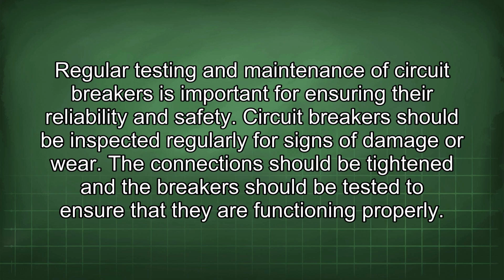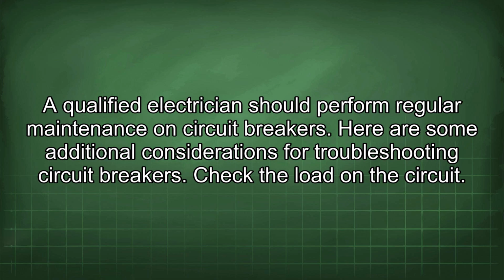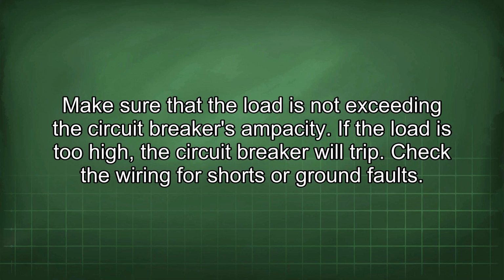Circuit breakers should be inspected regularly for signs of damage or wear. The connections should be tightened and the breakers should be tested to ensure that they are functioning properly. A qualified electrician should perform regular maintenance on circuit breakers. Here are some additional considerations for troubleshooting circuit breakers. Check the load on the circuit. Make sure that the load is not exceeding the circuit breaker's ampacity. If the load is too high, the circuit breaker will trip.